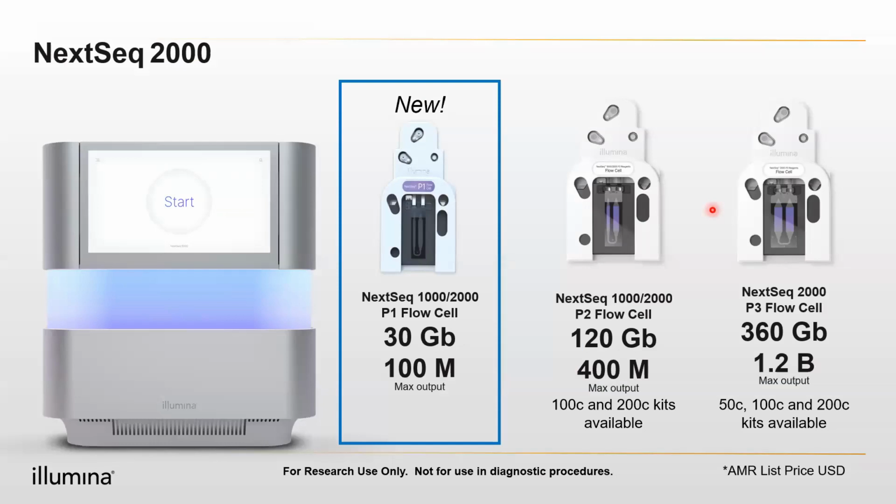Coming on to our next upgrade, that is your NextSeq 2000. Here, with the NextSeq 2000, Illumina has made major advancement in this machine. Basically this machine is fluidics free, and so basically less maintenance. You need not perform any wash. All the fluidics are basically built onto the cartridge itself. And it has also upgraded its imaging modules and the camera, so it's higher resolution.